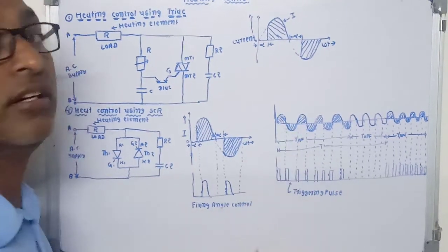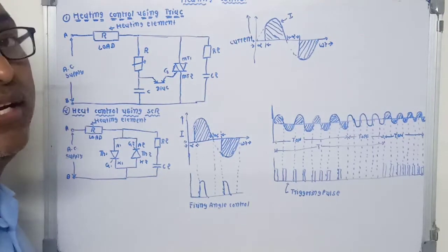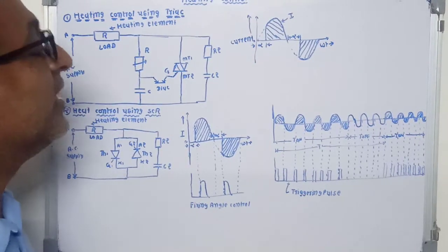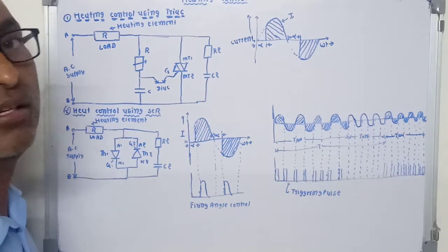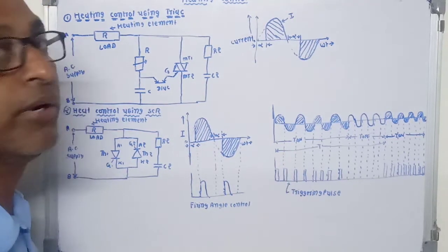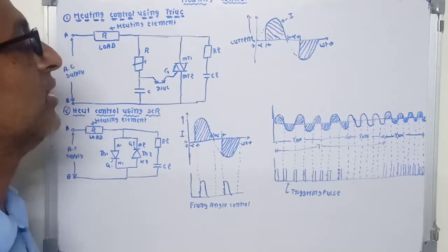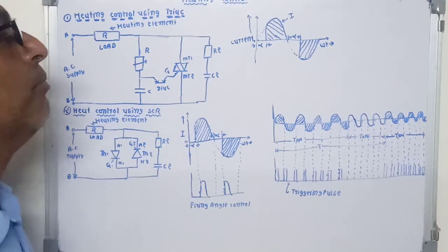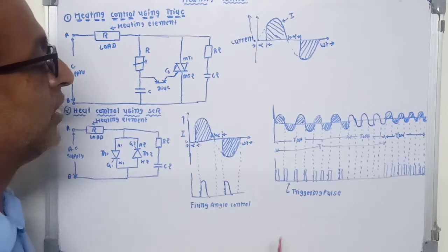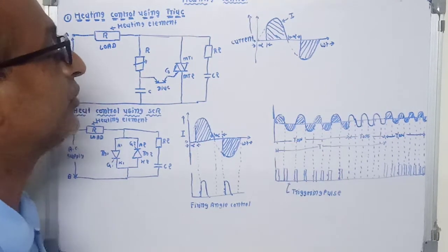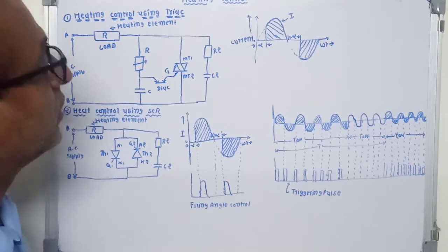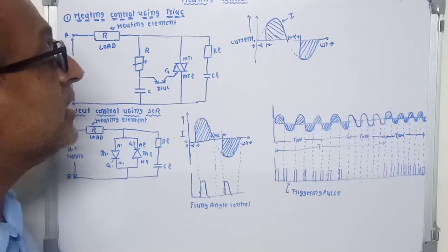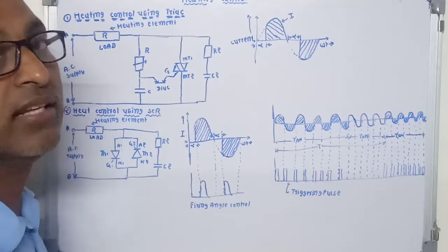To overcome this power factor problem, a second method is used. In this method, the thyristor is turned on for some input cycles and turned off for other cycles, eliminating the power factor problem. The thyristor operates at full half cycles with firing angle alpha equal to zero, so there is no effect on the power factor. This method is called integral cycle control, and heating control is achieved by changing the turn-on and turn-off periods.